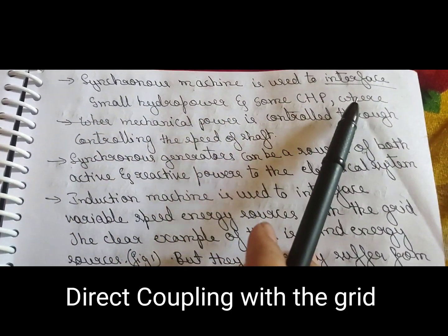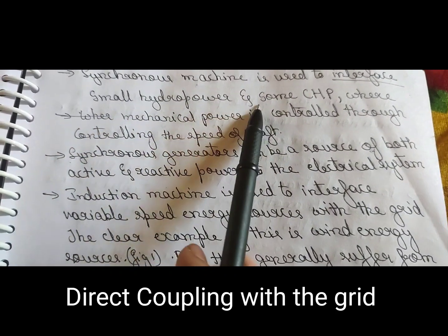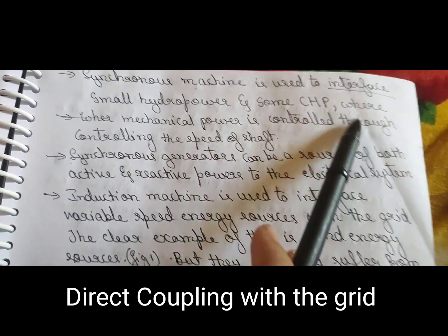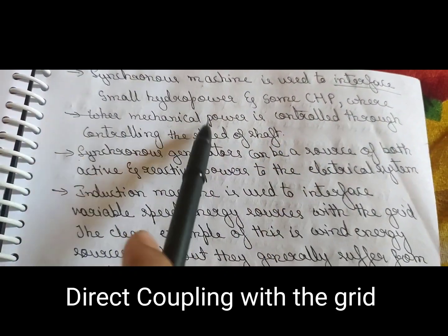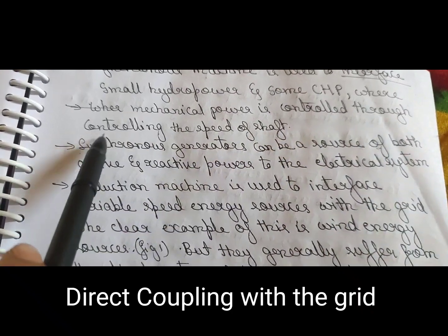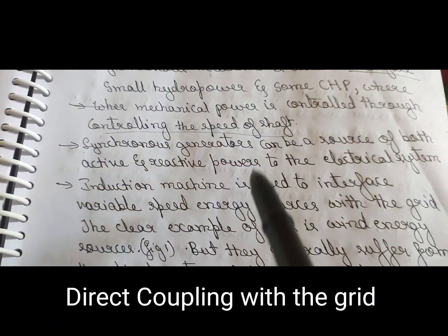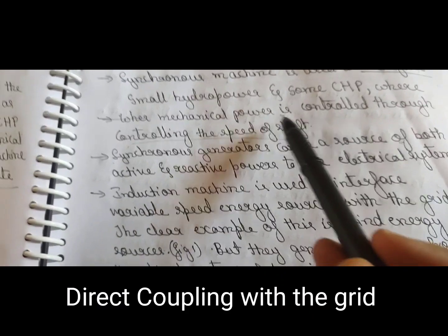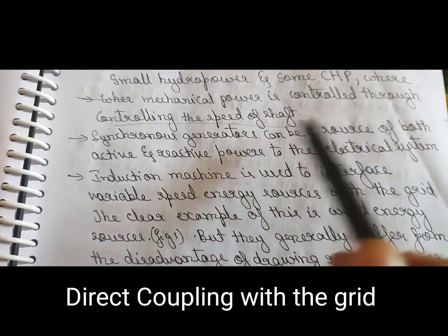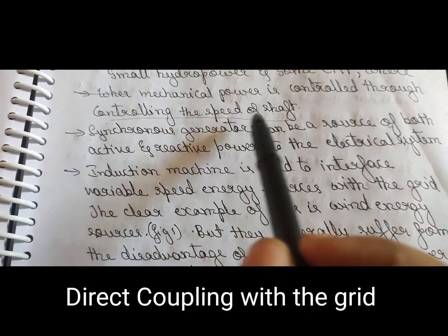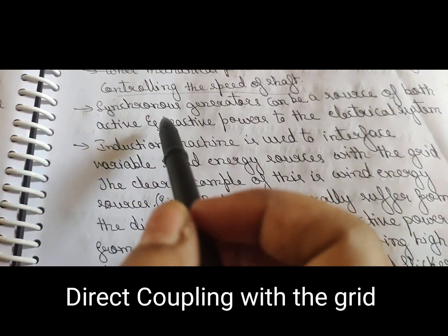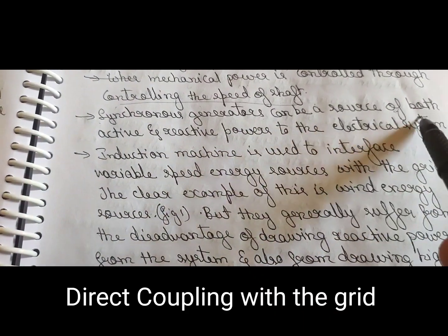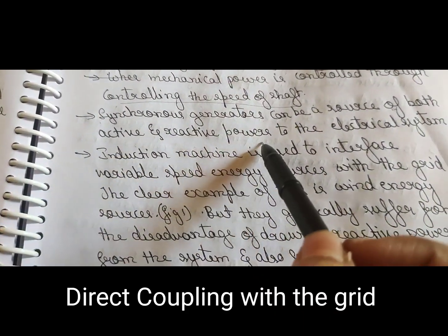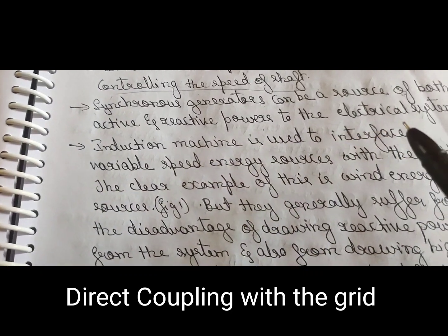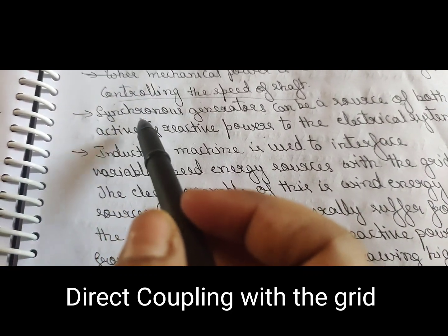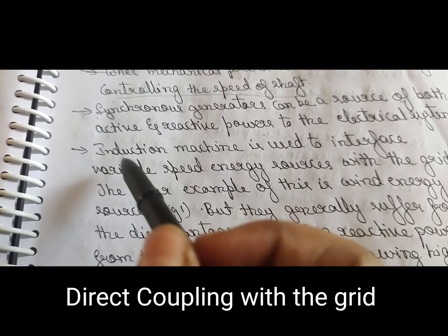is used to interface small hydropower and some CHP, that is combined heat power, where mechanical power is controlled by controlling the speed of the shaft. So here mechanical power is controlled through what? Controlling the speed of the shaft. A synchronous generator can be a source of both active and reactive power to the electrical system. So it will generate and it will absorb reactive power.